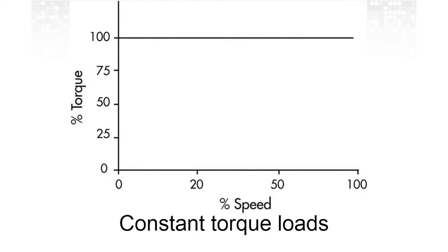For the constant torque motor, oddly enough, it's a straight line when you're plotting torque versus speed. So you don't get a lot of savings. You get 50% savings if you can reduce the speed 50%. But if you only reduce the speed 10%, you only get 10% savings.